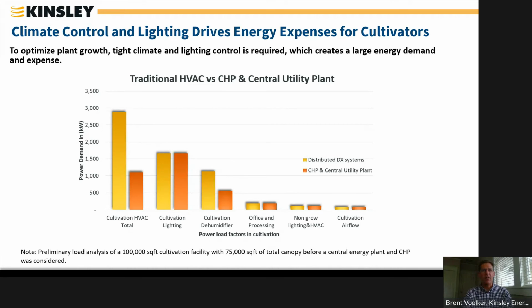There are applications with high peak demands and periods of much lower demand, where you could use any qualified generator to do peak shaving, because the utility often charges you two ways: for demand at that high peak, and for the number of kilowatt hours you consume. When you hit a very high peak, you pay for that because they have to provide all the copper, distribution and transmission necessary to deliver that power, even if you only demand it for 15 minutes out of the day. So they charge you for demand, and also an energy charge for the kilowatt hours.